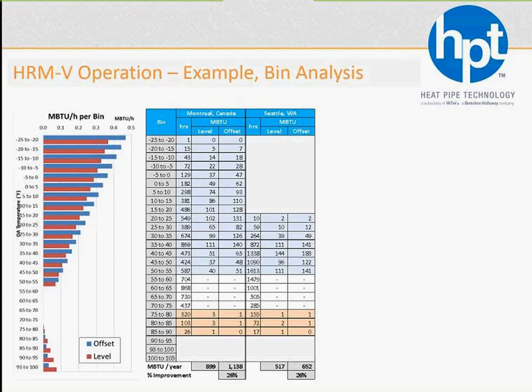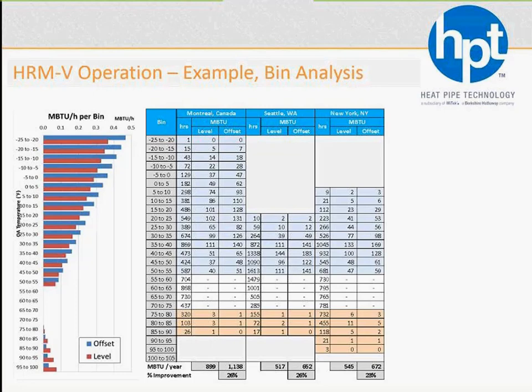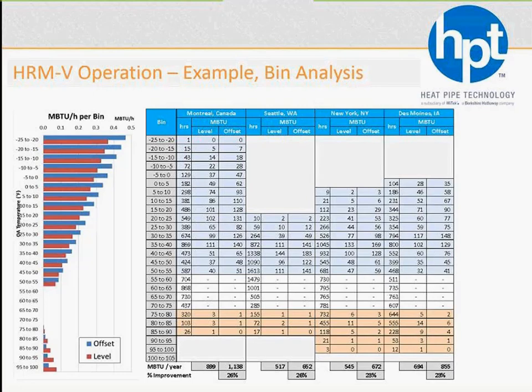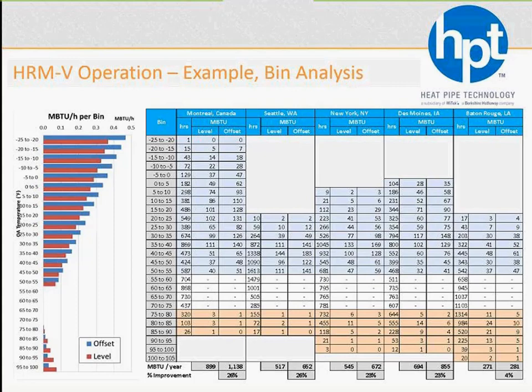The other end of the continent, Seattle: fewer bins, same difference between level and offset, actually 26% better recovery in winter as well. Another city, New York: fewer bins, but more than Seattle, a fairly meaningful difference, about 23% if you optimize for winter heating. Des Moines, Iowa: another 23% difference in favor of optimized winter heating, and offset meaning in favor of winter recovery. Now representing the South, the great city of Baton Rouge, it's almost a toss-up. You can actually get by with or without an offset. There's about a 4% difference in performance.